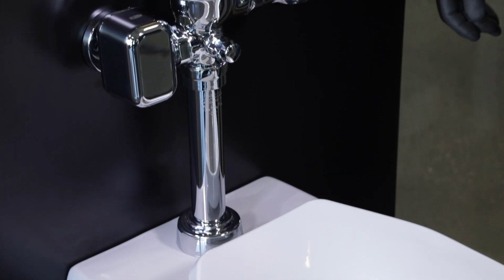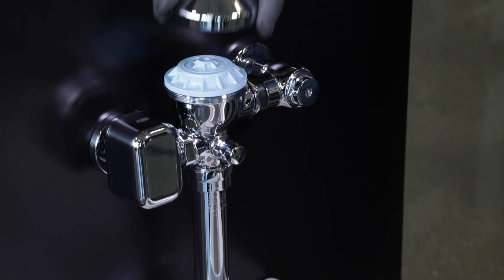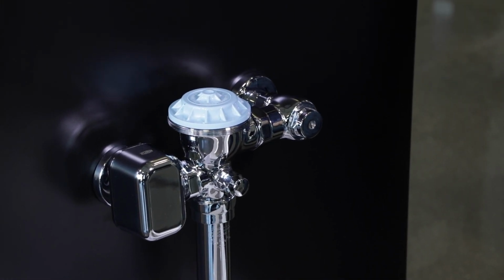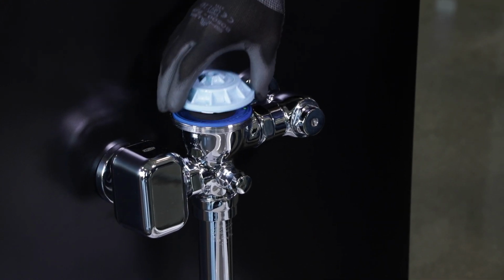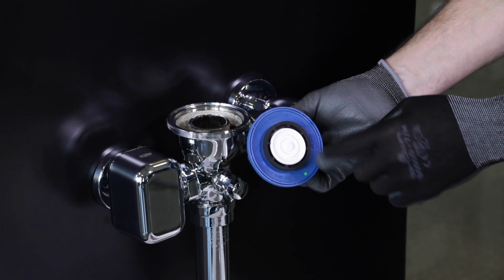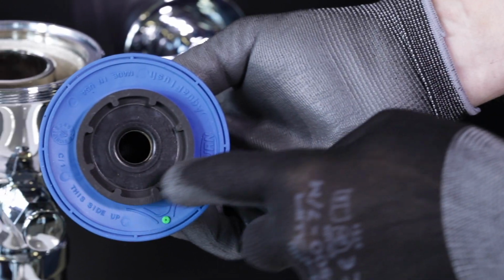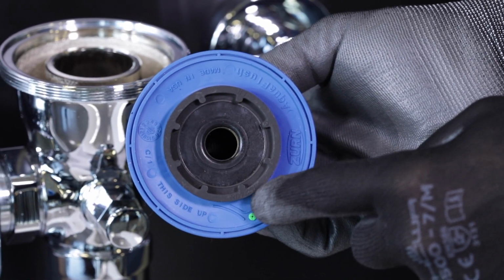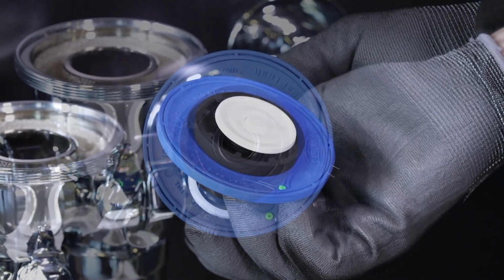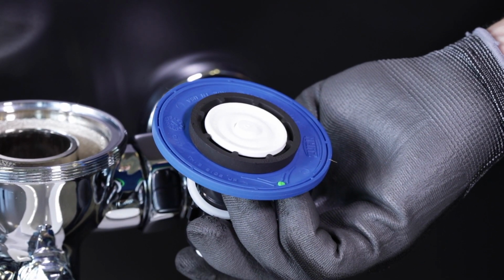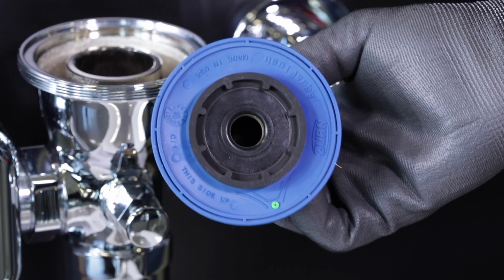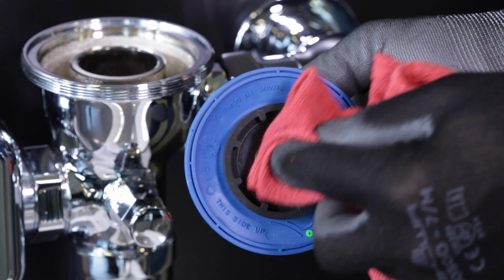Next, check for foreign material that could prevent the trip mechanism from seating properly. Remove the cap and the inner blue diaphragm cap. Remove the trip unit. This is the trip mechanism. This is the seat. Any buildup of material and it will not seat properly, which affects operation. Remove any material and wipe the parts clean using a clean cloth.